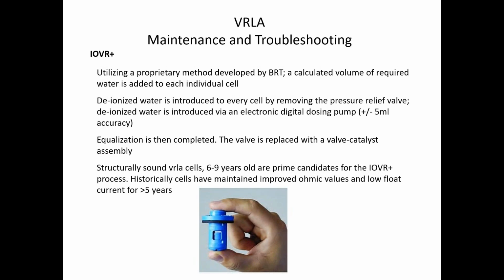I don't want to get too much into this, but just to let you know, there is remediation or a service for batteries that are exhibiting signs of dry out. And that's more often than not the failure mode of valve regulated batteries. It's just a function. I mentioned the one-way relief valve. They're not designed to have water reintroduced to them or any other work done to them, but we've pioneered a process by which we actually can rejuvenate and recover capacity in valve regulated batteries.